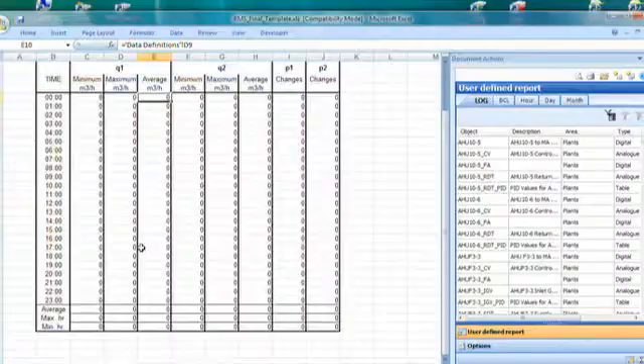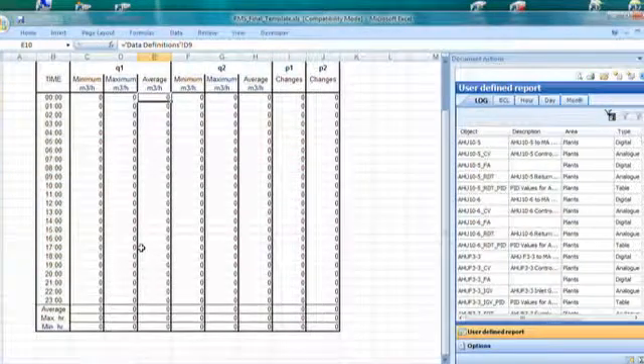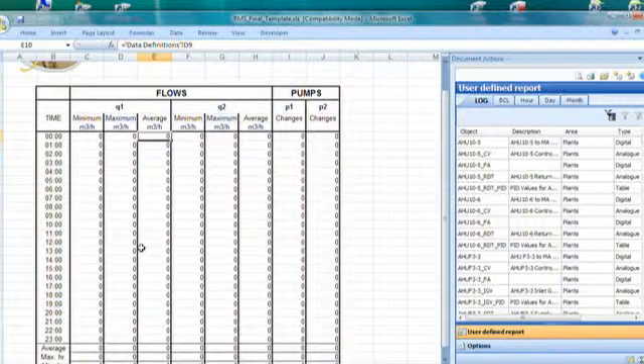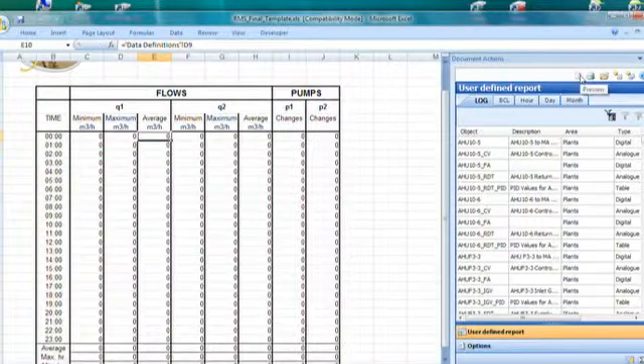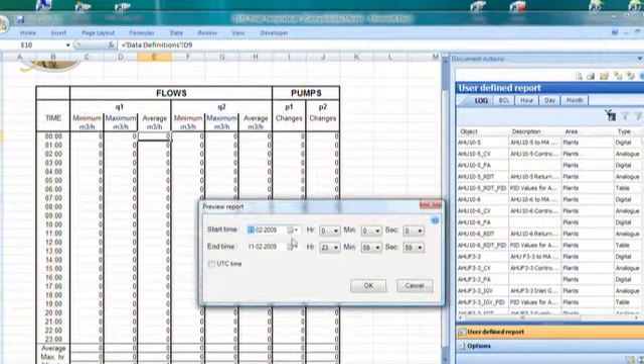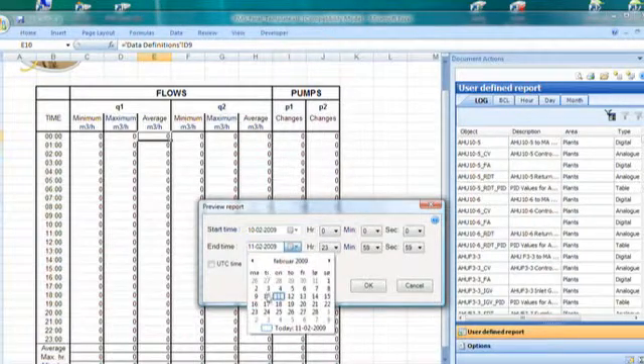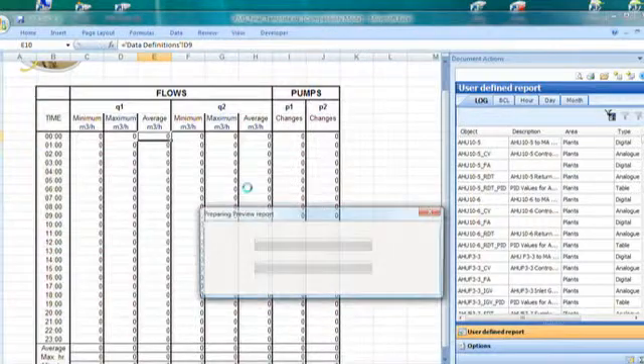Let's first take a look at the log report I have created in this sample — a log report consisting of values for two flow meters, Q1 and Q2, and two pumps, P1 and P2. Let's take a preview of the report. We select the report date first in RMS, then click OK to preview. I have included three different values for the flow meters: minimum, maximum, and average. For the pumps, I have included the number of state changes during the hour and during the day in the calculated sum.